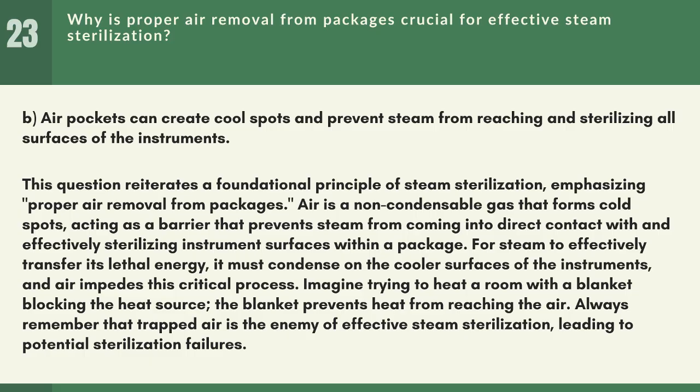For steam to effectively transfer its lethal energy, it must condense on the cooler surfaces of the instruments, and air impedes this critical process. Imagine trying to heat a room with a blanket blocking the heat source. The blanket prevents heat from reaching the air. Always remember that trapped air is the enemy of effective steam sterilization, leading to potential sterilization failures.